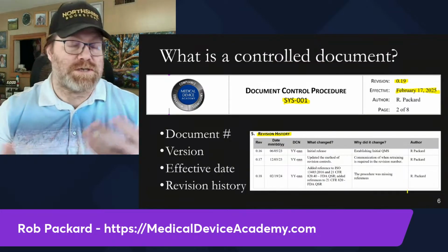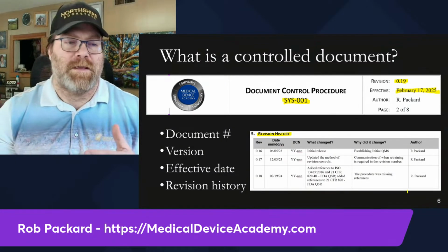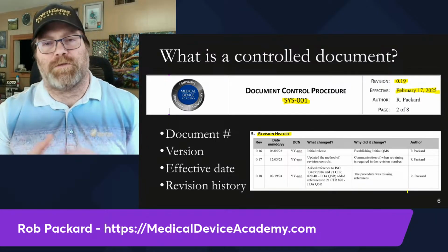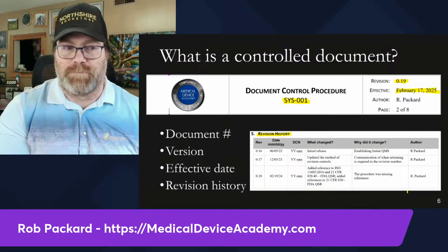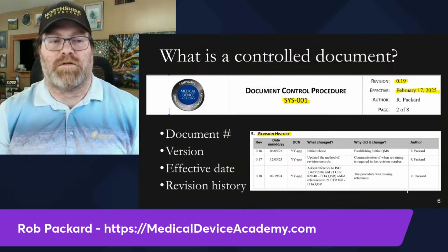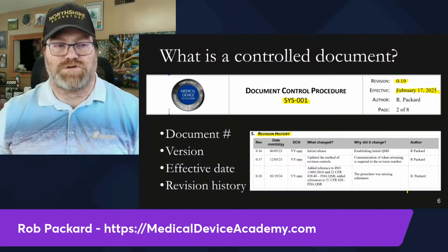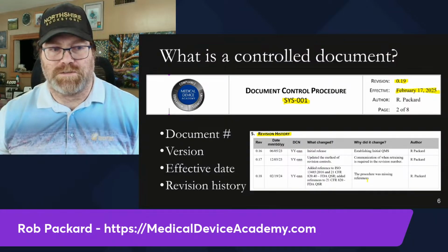If you made multiple changes, they may look at more than that, but in the short amount of time, probably 6 weeks between stage 1 and stage 2, you probably only made the revisions they told you to make, and therefore they're just looking at, they want to see evidence in your revision history that you made those changes. So they're going to look at what changed.